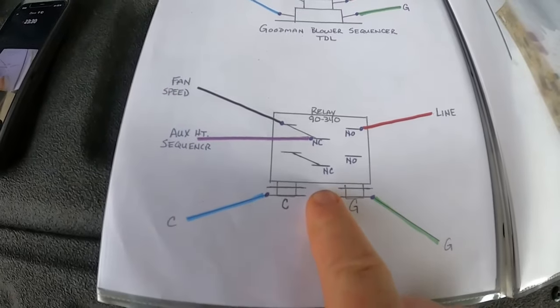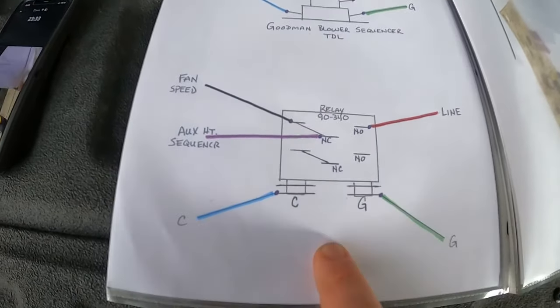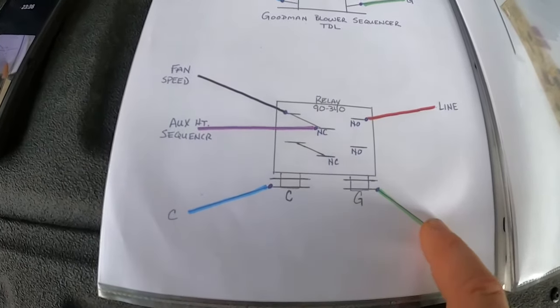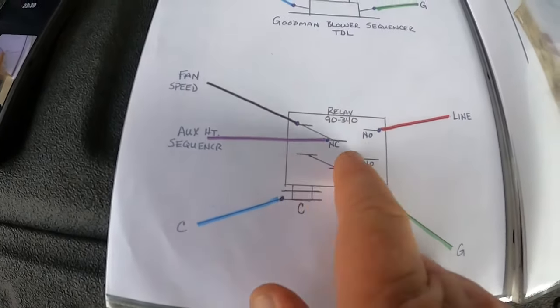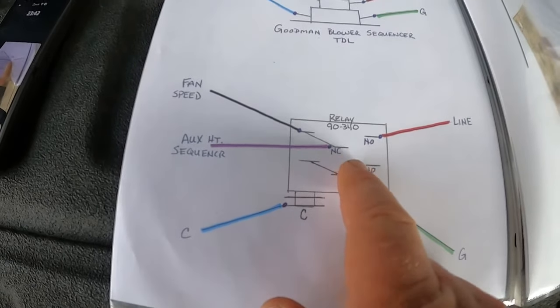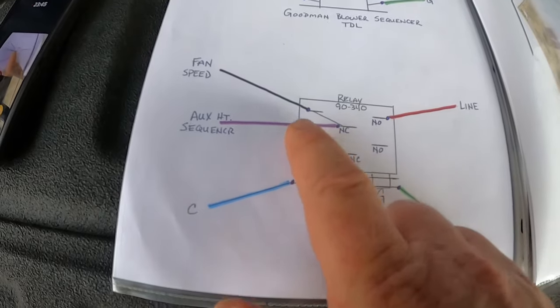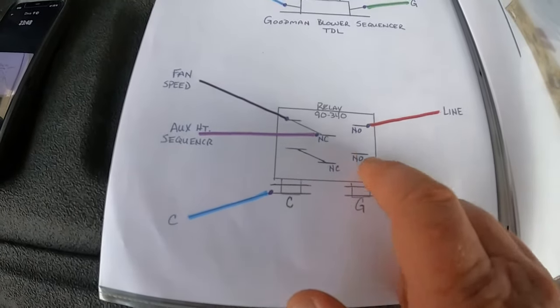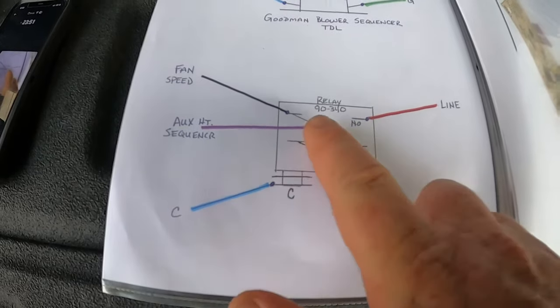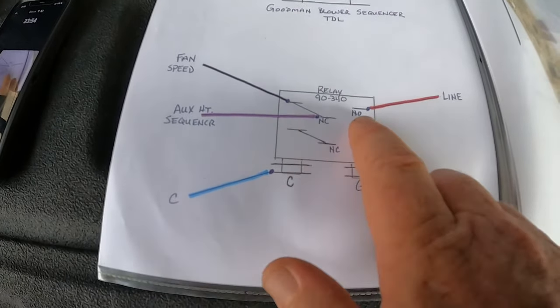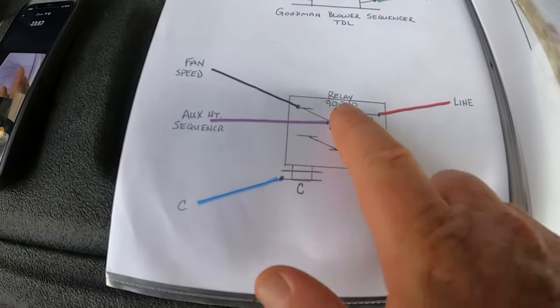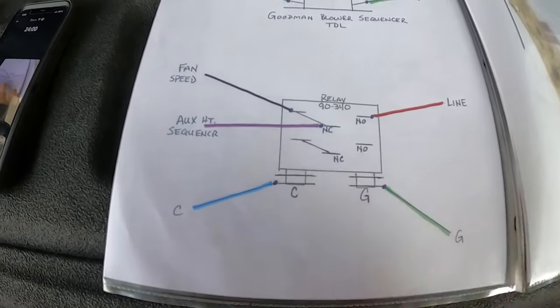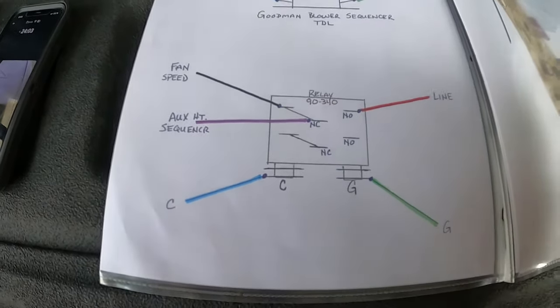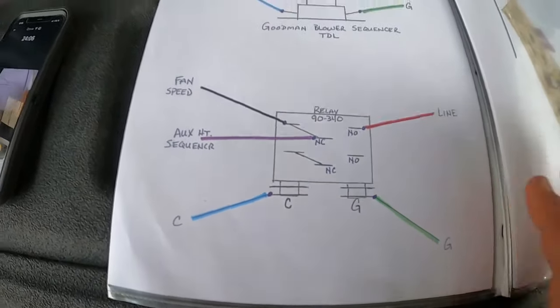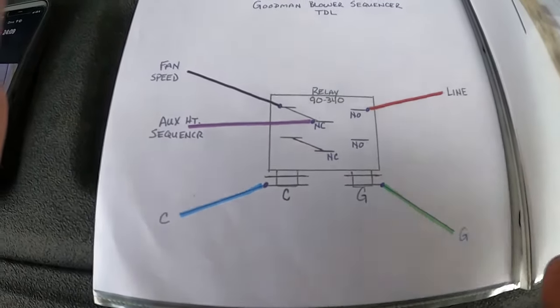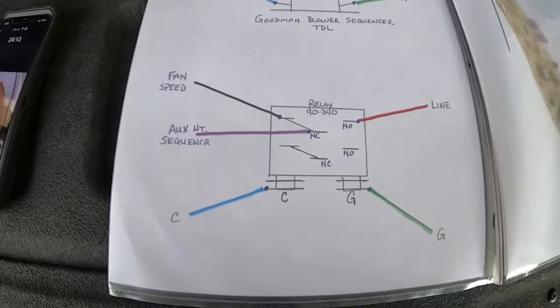You want to be able to put your disconnect back in, breaker back on, 0 amps. Energize G, get airflow with no amps on your heat strips. De-energize G, blower shuts off, no amps. Energize auxiliary, heat strips come on, blower comes on. De-energize auxiliary in emergency, heat strips shut off, blower shuts off, 0 amps. And that's the key. You want to make sure that if you don't have a call on anything, there's no amp draw. Once you've done that, you've confirmed you've got it wired up right.